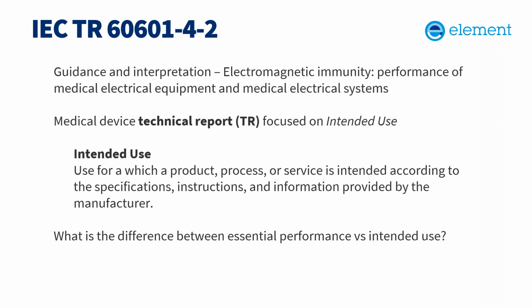So in addition to 60601-1-2 and any of the particular -2 standards, one more item should be looked at. So IEC TR 60601-4-2. It's not strictly a standard, it's a technical report. That's why it's IEC TR. It's a technical report for electromagnetic immunity for medical devices. So it is on the FDA consensus standards list, and FDA reviewers are asking for testing to it.